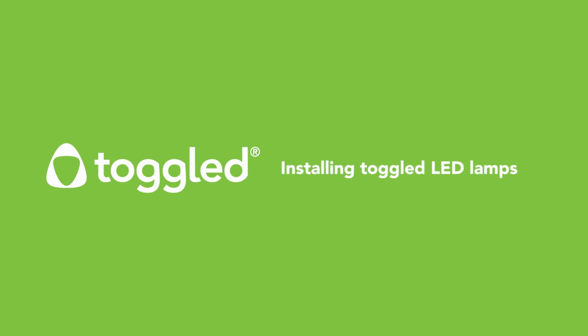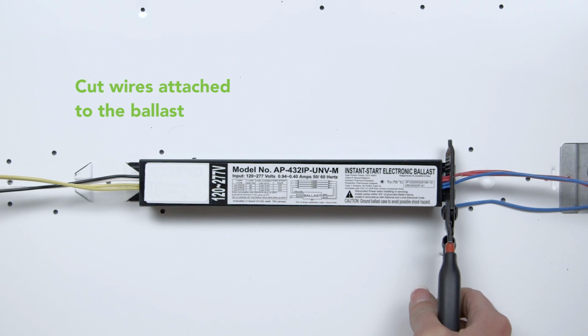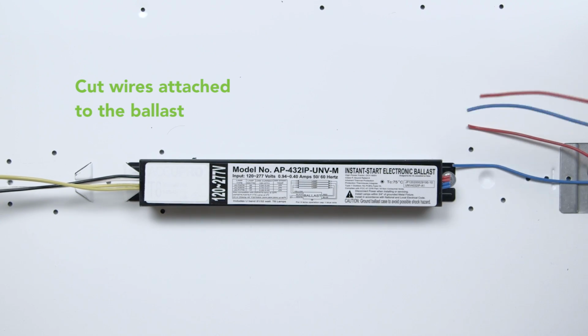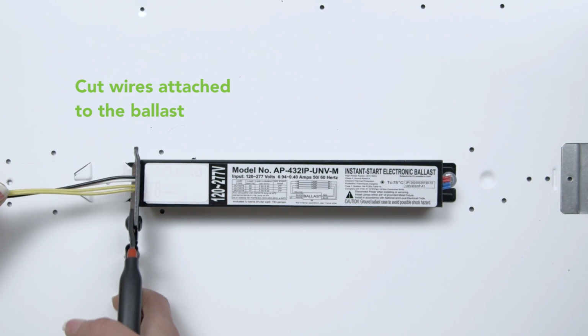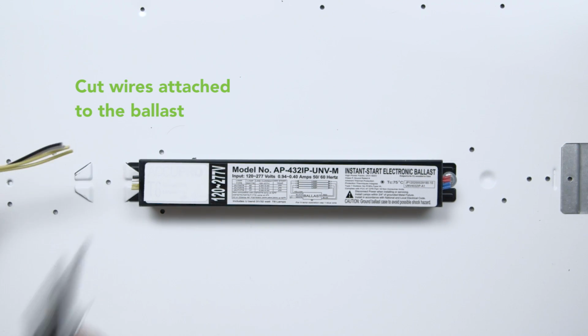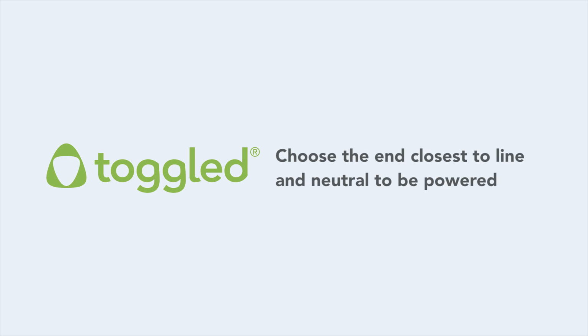You are now ready to begin installation of your Toggled LED lamps. Cut all wires attached to the existing ballast as closely as possible to the ballast. If you choose to leave the ballast in place, it's not necessary to insulate wire ends attached to the ballast, as power to the ballast has been cut. Choose the end closest to line and neutral to be powered. Toggled tubes accept power at only one end.